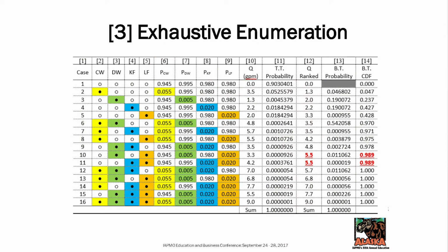This method, you can use this method to come up with the 99th percentile. It's called exhaustive enumeration. This is what runs on the macros in a spreadsheet. So if you've tried downloading this water demand calculator from IAPMO site, you're going to get a Microsoft Office warning. This file has macros. It could contain viruses. Beware. That's just standard. If any spreadsheet has macros, you're going to get that warning. But the spreadsheet is safe to download. This is the only thing that runs on macros.